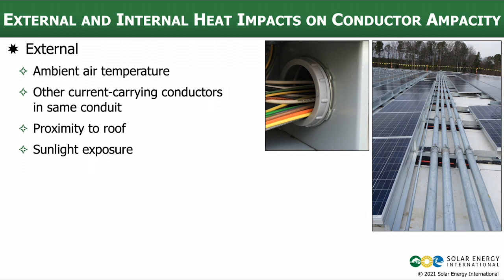Proximity to the roof can certainly make a difference. When we have conductors in raceways or behind modules that are really close to the roof surface, the direct sun and reduced airflow can cause them to operate at higher temperatures, especially with direct sunlight exposure. Something sitting in the sun is going to be hotter than the ambient air temperature. All of these external factors can impact the temperature of a conductor and thus its ampacity.